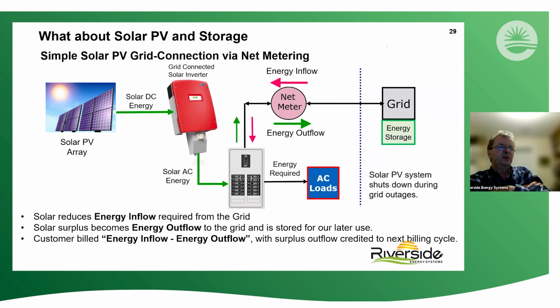A simple grid-connected system under a net metering program or self-generation program lets us do that. It interacts with the grid to reduce how much we buy, and outflows to the grid when producing surplus. Under net metering, that energy can be stored and used later. The downside is that the PV system shuts down during a grid outage.